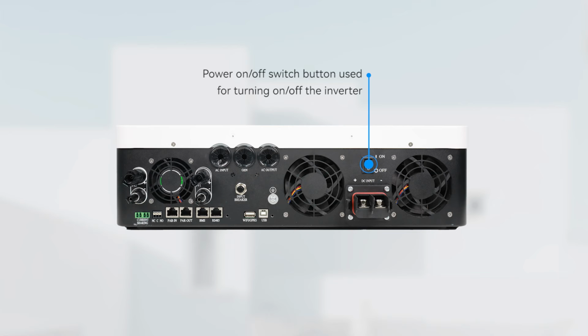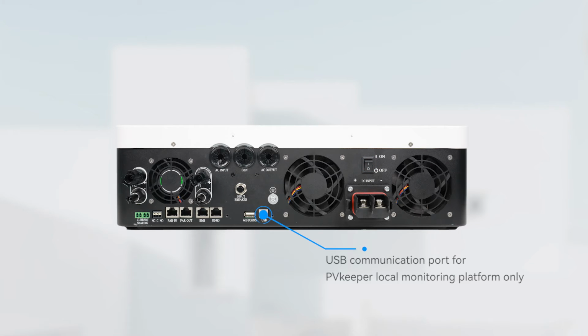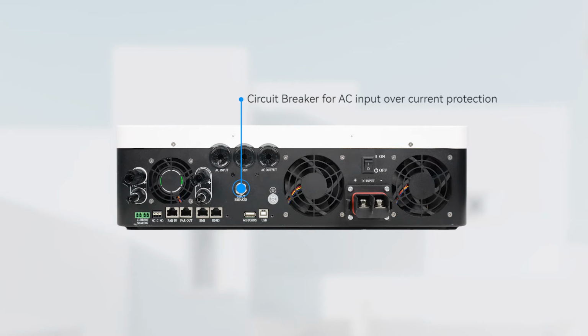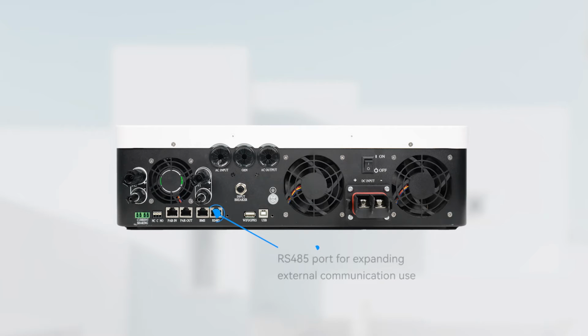Power on and off switch button used for turning on and off the inverter. USB communication port for PV keeper local monitoring platform only. Wi-Fi and GPRS port connect to Wi-Fi or GPRS-F monitoring device. Circuit breaker for AC input over current protection. RS485 port for expanding external communication use.